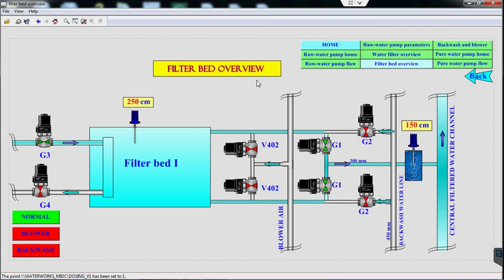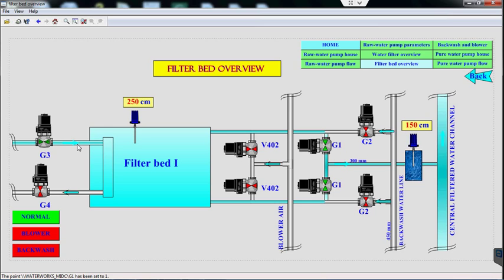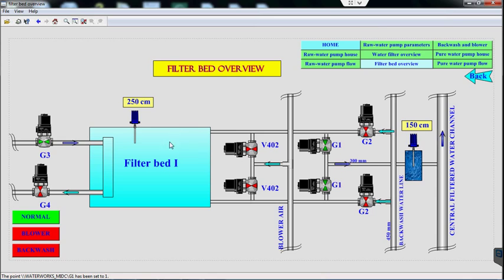Filter bed overview. The filter bed is provided with a raw water inlet valve G3 and pure water outlet valve G1, blower air inlet valve V402, backwash water inlet valve G2, and backwash water drain valve G4. During the backwash cycle, pure water is stopped. Blower air fluidizes the bed for a predetermined time and backwash water cleans the bed. The sequence of operation is automatic and divided into four sequences. In Sequence 1, normal mode, raw water inlet valve G3 and pure water outlet valve G1 are open; all other valves are kept closed. An ultrasonic level transmitter measures the bed water level and a capacitance-type level transmitter measures the pure water open chamber level. If the filter bed level increases or the pure water open channel level decreases beyond a predetermined level, the backwash sequence will automatically start.